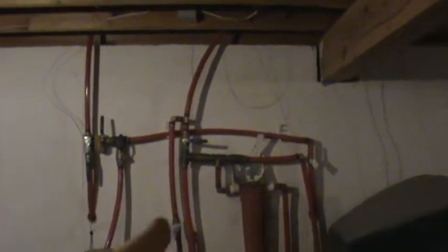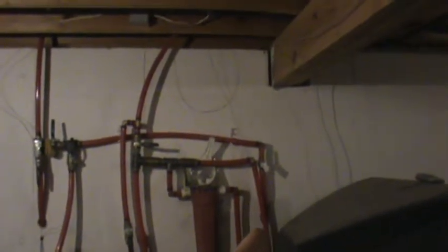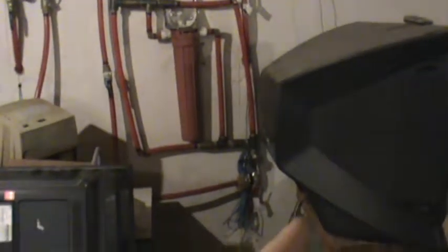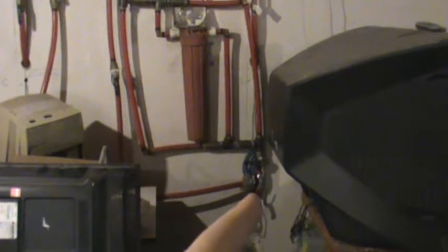Now, these tanks, there's one on one side and one on the other. You can kind of see the send to one is here. It goes through the wall there. And there, kind of behind that pipe, is the other send. And then at the bottom, you probably can't see it, but maybe, yeah, you can see this one at least. There's a return coming out of the wall. So basically it goes into the tank at the top and comes out of the tank at the bottom.